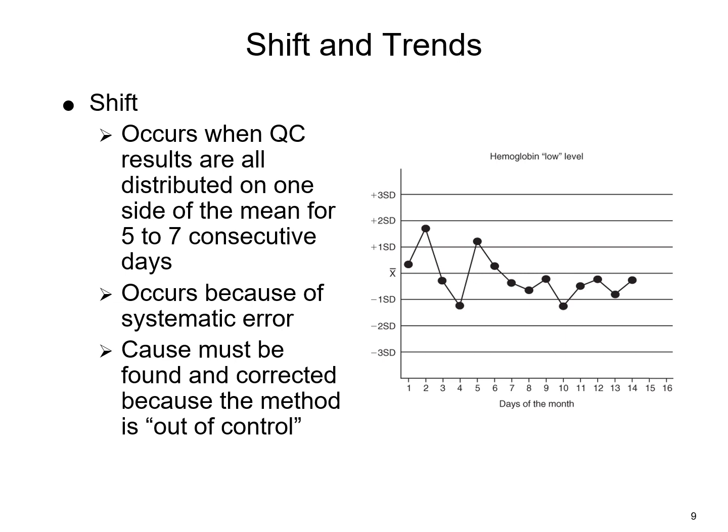So you could look at your QC material. Did this start happening once we opened up a new lot of QC or a new vial of QC? Is it something on the instrument that's malfunctioning that you need to look at? So you've got to find the cause of whatever's causing this stuff to start to look out of control, and you've got to fix that problem before it gets to a point where it shuts your whole analyzer down and you're not operating for the day.